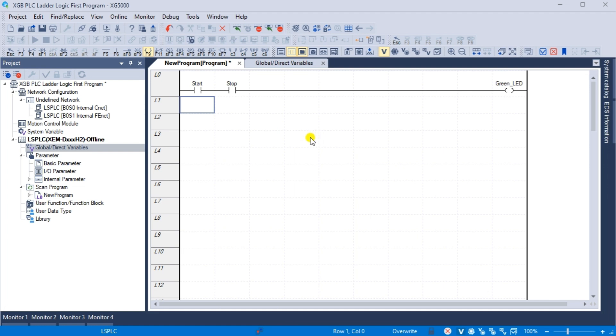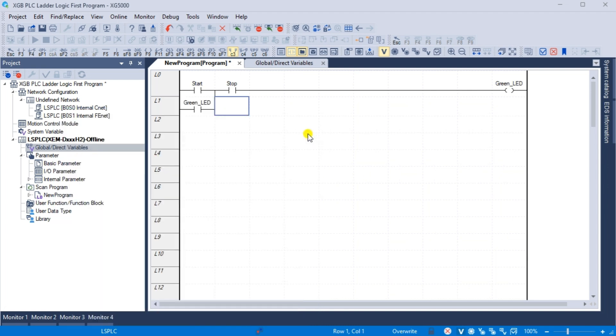We can place the normally open or contact under the start contact. This will be the input for our green LED variable. In a start-stop circuit, this is called the sealing contact. Since the start input is momentary, we must ensure that the green LED light stays on. Once the green LED light is on, this will essentially bypass the start and the only input to stop the output will be the stop contact.